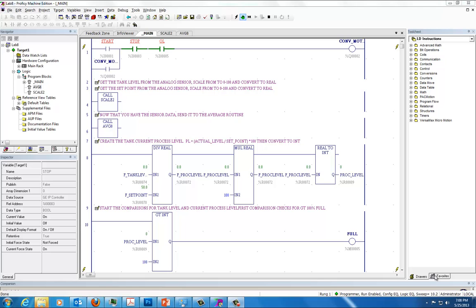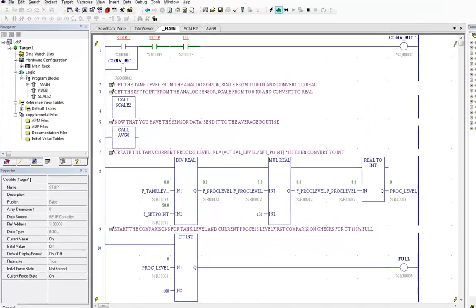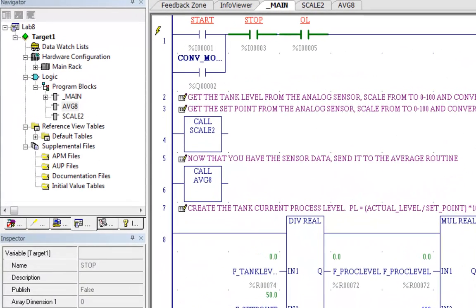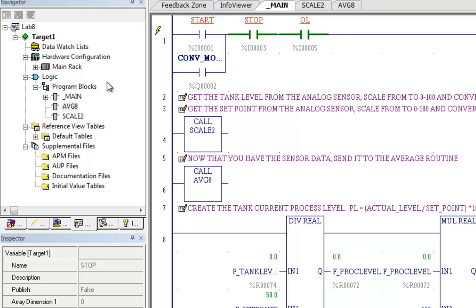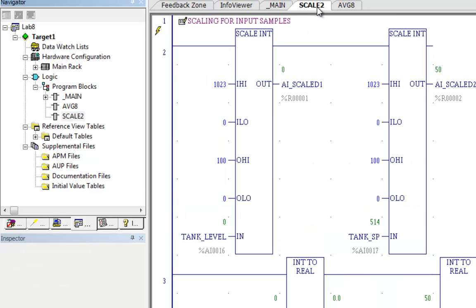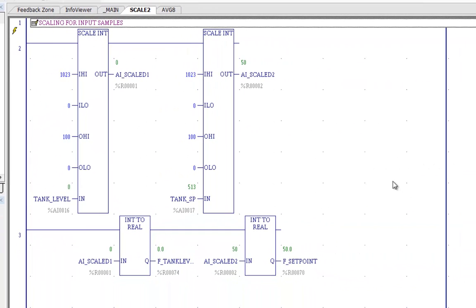We've got the program here and I'm introducing a few new concepts to you and one of them is the subroutine call. I've created two subroutines, one called scale2 for scaling the two analog inputs and the other one is average8. And what I did is I'm averaging my input values to create a more consistent value. For the first we're going to look at scale2. When it gets to this instruction it will call a program called scale2. If you look over here in program blocks you'll see that I created another routine, another program. We have our main, average8, AVG8 and now scale2. I have it already loaded up here in the tab so I'm going to click on this tab and there's some programs.